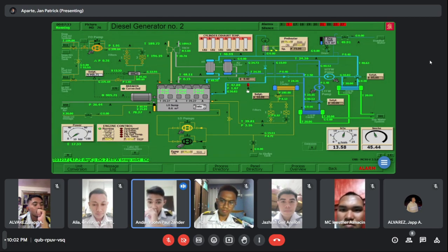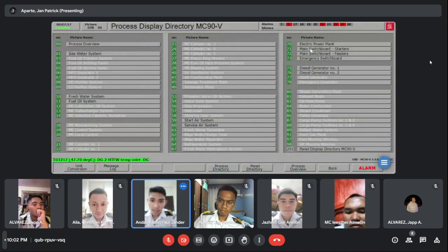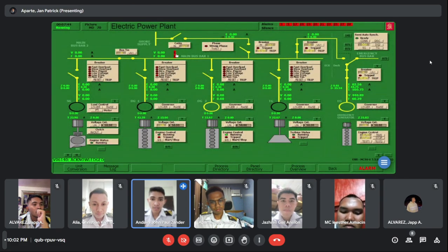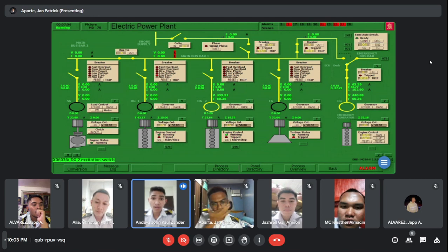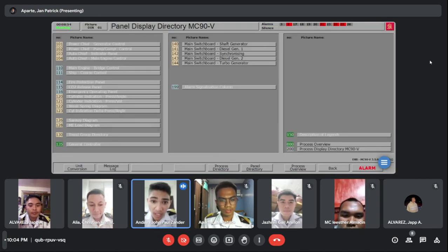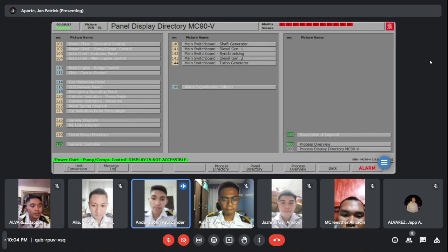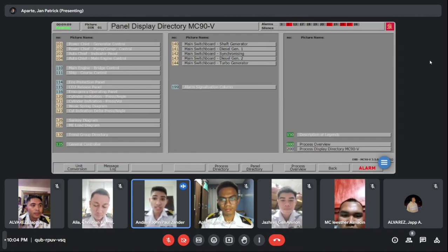After that, go to the switch to turn on the voltage controller. Just go to the electric panel in the electricity section. Then switch on the voltage control of DG number 2. Okay. After the voltage controller in the electric power plant, go to MD102, which is the pump or compressor control. Switch on remote operations of generators and set priority settings. So set DG1 to priority 1 and then DG2 to priority 2. And make sure to click auto, both must be on auto.